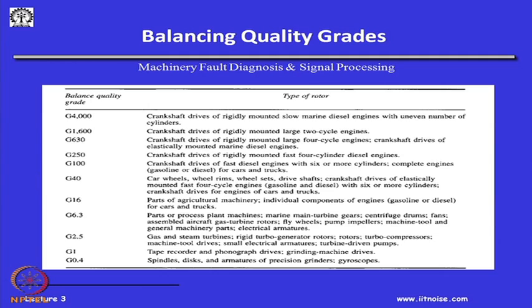Okay. Now, the question is, with this brief understanding of unbalance, what effects can it have on systems? Many machinery components actually start failing because of unbalance. See what happens, unbalance gives rise to excessive forces at the supports. So, the supports, the bearings, will then get damaged. So, we may be alarmed because of a bearing failure, but the initial problem could be something else.